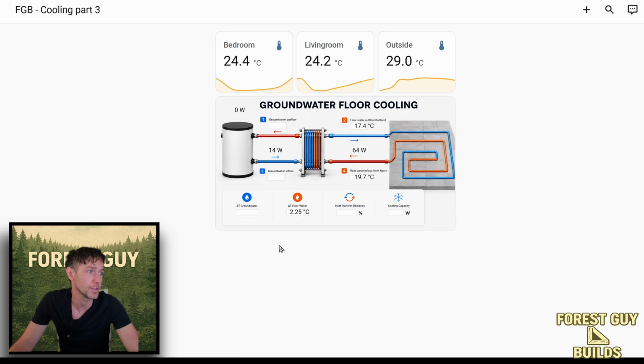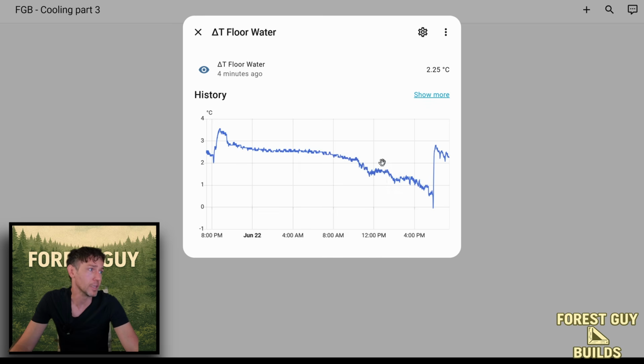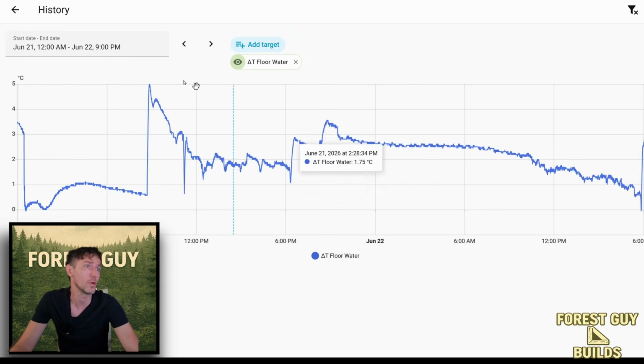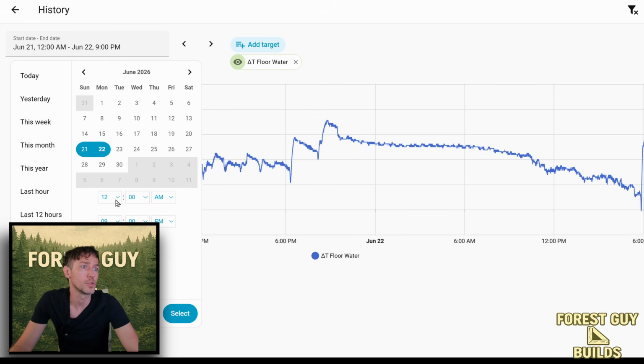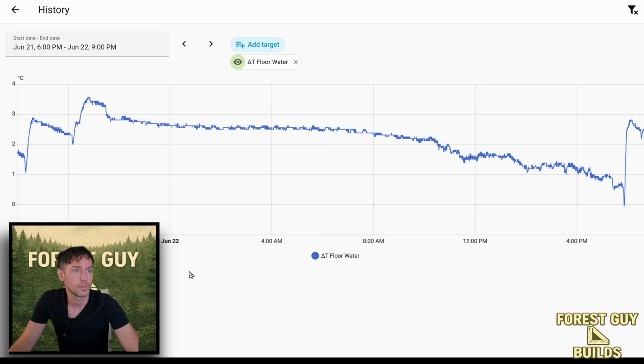For those interested in the temperatures throughout the days, looking at the delta, the difference between the inflow and outflow, let me show that on a smaller time frame. This was the temperature difference from yesterday evening until this evening. We see it was sometimes around 3, 3.6 degrees, and in general it's about 2.